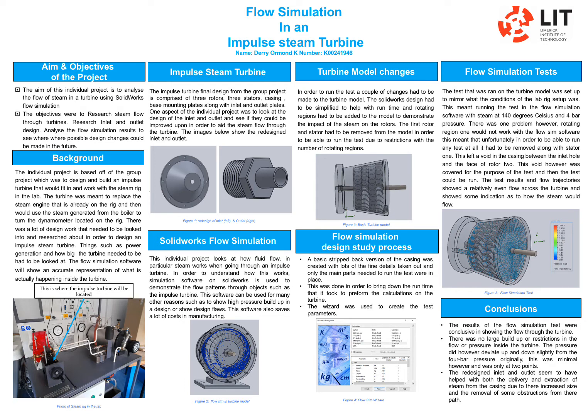There didn't seem to be any high pressure areas or any blockages within the turbine itself. The results showed even flow throughout the whole turbine, with no large build-ups or restrictions in pressure. The redesign of the inlet and outlet seemed to aid the flow of steam into the turbine and out the far side.